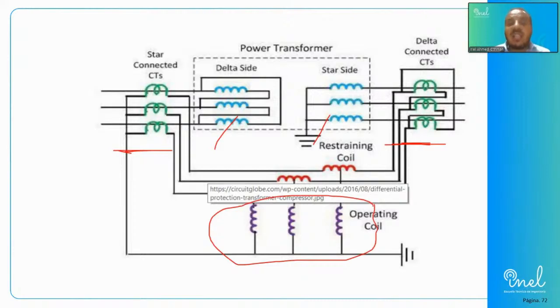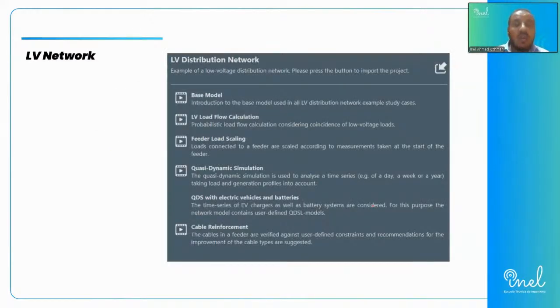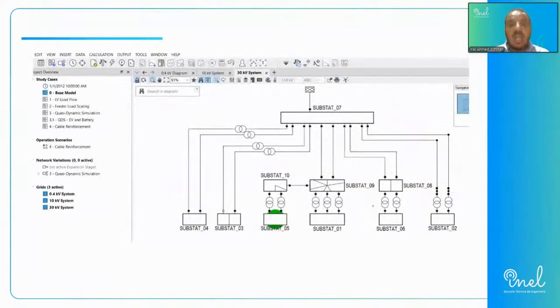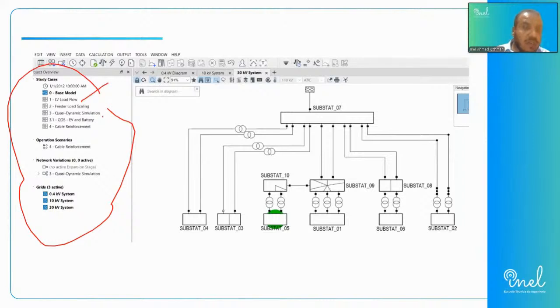So either we can use the ready-made ones. There is a library which includes protection and differential protection. We can use those examples, or we can build our customized differential protection scheme. So we can find some examples for load flow, for low voltage network, distribution voltage. And from here we will also find the case studies. So we have a case study for load flow, we have a case study for dynamic or for cable, and from there we can insert some transformer if we need to focus also on the transformer segment.